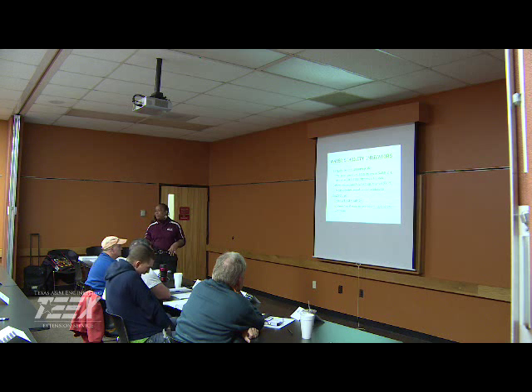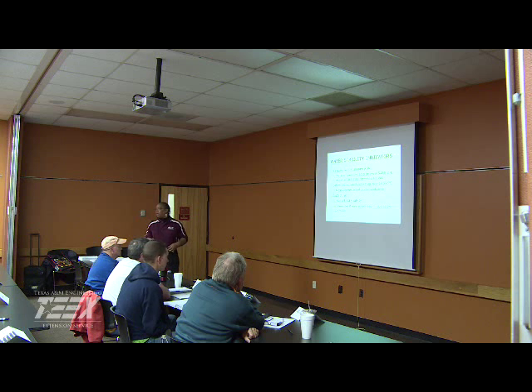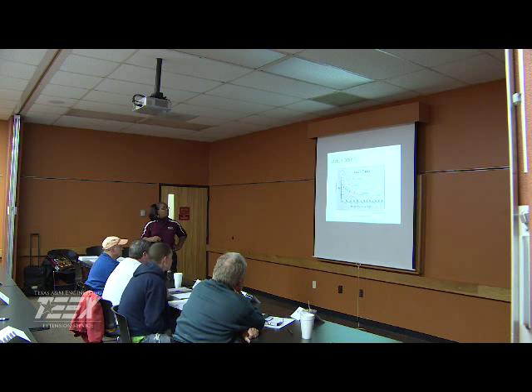Put one T and an S on there, because an operator can do that, and much of it can be done in the field. We use the pH and the alkalinity, and we plot it on this scale. So this is the Baylis curve here. And the way it reads, the green, of course, is your stable line. So we want to make sure that at all times we're between this red and yellow line here.